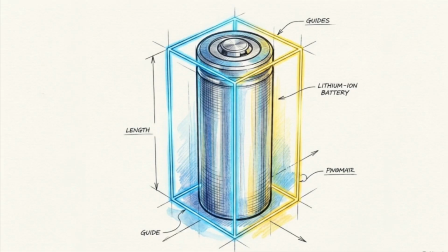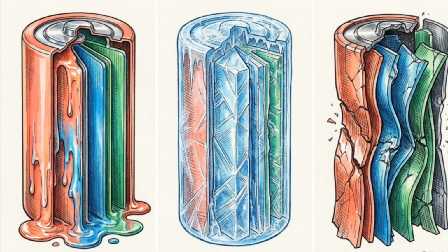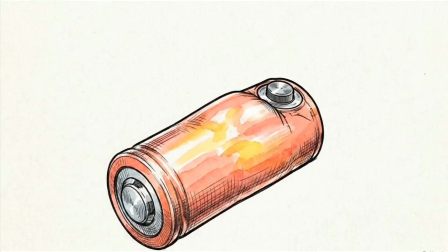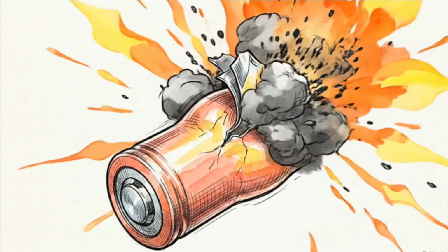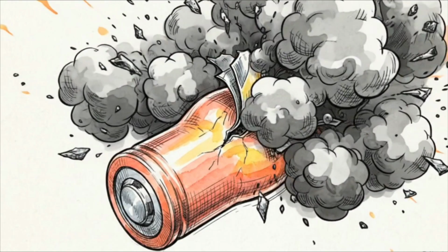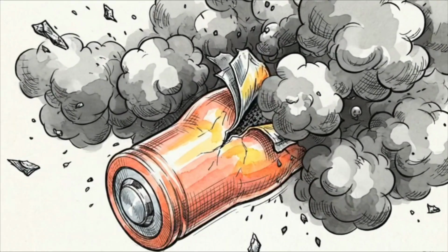A single lithium-ion cell operates safely only within very narrow physical parameters. If it gets too hot, too cold, or if energy is pulled from it too quickly, the internal chemical structure degrades. Pushing a cell past these limits causes a rapid exothermic reaction called thermal runaway. Pressure builds and the cell violently vents heat and particulate matter.